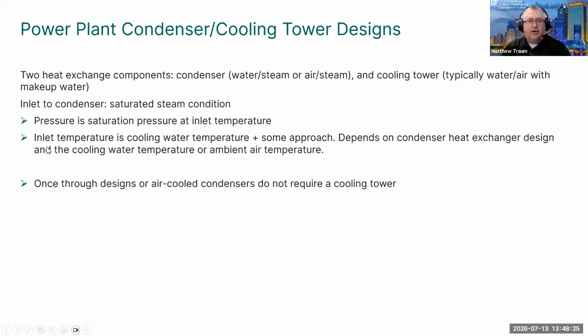Laura, sorry to interrupt you. There's a question in the chat which I can read for the benefit of the recording, which is: even if you are cooling with water, you are still going to have an air cooler to cool the water you heated up? Yes, most likely. As I said, if you have a closed cooling water circuit, you've picked up heat energy that you need to reject somehow. Typically, as I said, that is through a wet cooling tower, which involves an air element.